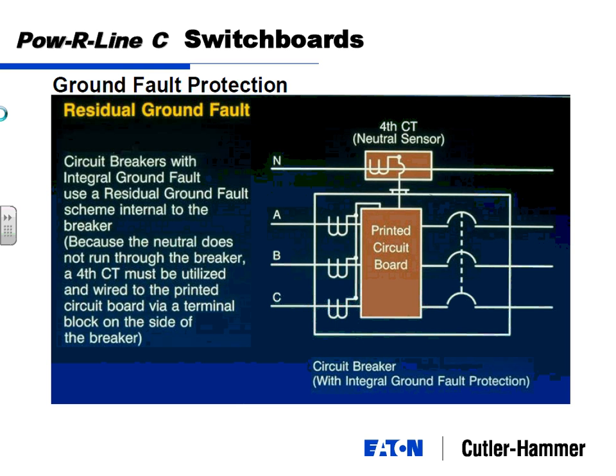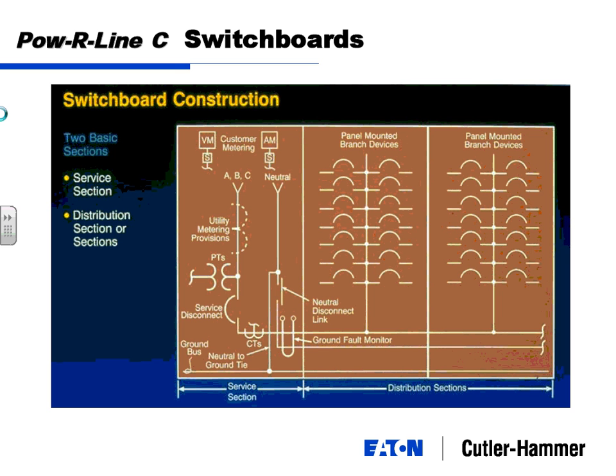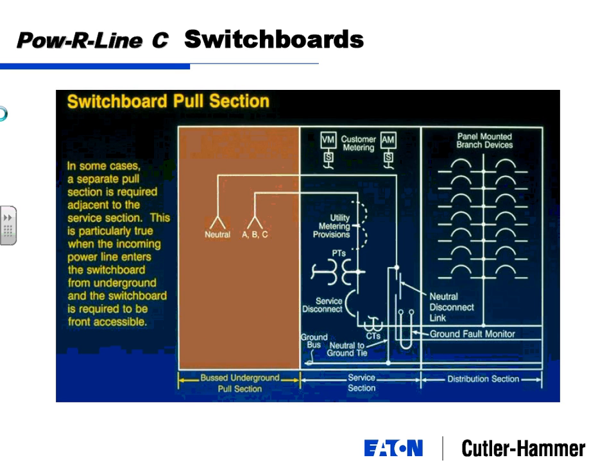So this frame here is your circuit breaker. All your CTs and everything, you don't have to do anything extra inside the circuit breaker. The shunt trip is built into the circuit breaker. The only thing extra you'd have to do is wire, if there's a neutral, a neutral CT, which we provide with it. You just got to run your cable through there. So you can see, to do it with a circuit breaker, it's almost doing nothing. We talked about the different switchboard construction, can just have a bunch of different configurations. Switchboards are custom assemblies. I don't think there's such a thing as any 2 switchboards that are the same, unless it's the same job.